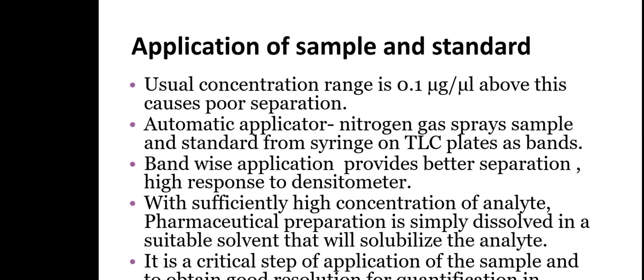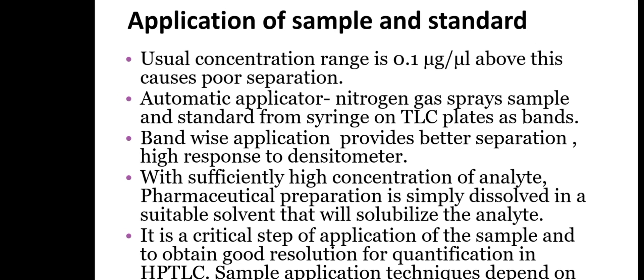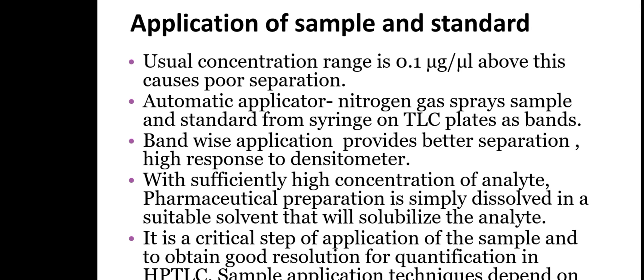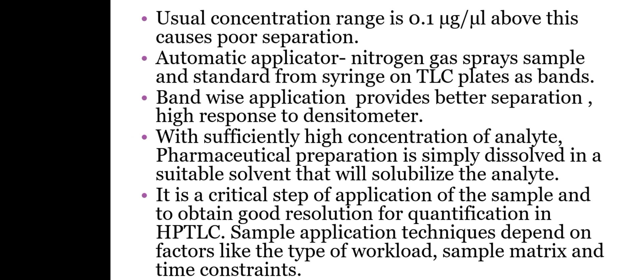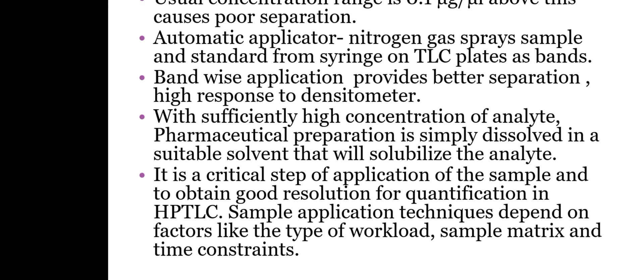For sample and standard application, the usual concentration range is 0.1 µg/µL; above this causes poor separation. An automatic applicator using nitrogen gas sprays the sample and standard from a syringe onto TLC plates as bands. Band-wise application provides better separation and high response to the densitometer. Pharmaceutical preparations are simply dissolved in a suitable solvent to solubilize the analyte. Sample application depends on factors like type of workload, sample matrix, and time constraints.